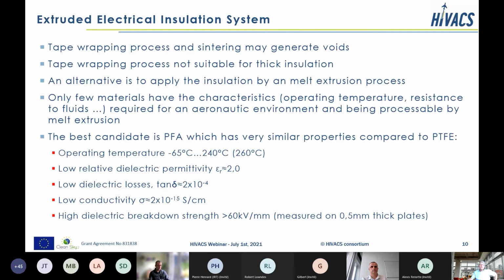So our conclusion is that the tape wrapping process is not a suitable process for high voltage cables, and that we should better use insulation which is applied by a melt extrusion process. There are only few materials which can be used for that, which have the required properties or properties which are close to what we use today, to the PTFE insulation.